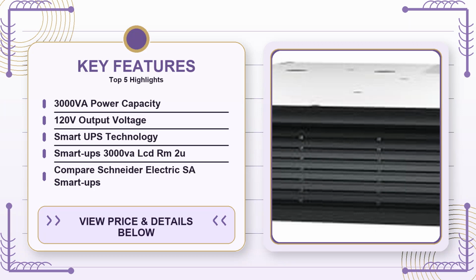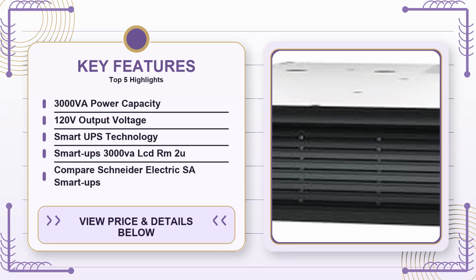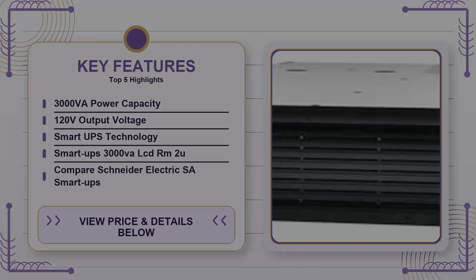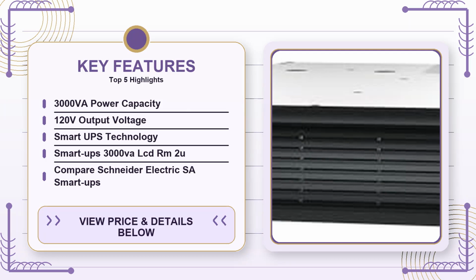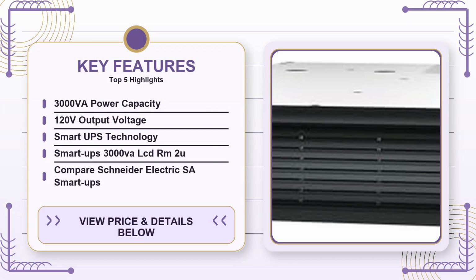Second, the 120V input restriction can be a stumbling block for those in regions where 230V is the standard. The unit is clearly aimed at the North American market, so if you're buying it for a data center that uses 230V, you'll have to add a step-down transformer or look for a different model that natively supports 230V. That extra equipment not only adds cost but also introduces another point of potential failure. For someone who thought they could plug the UPS straight into a standard European outlet, the surprise can be costly.